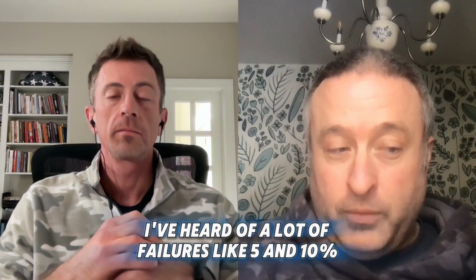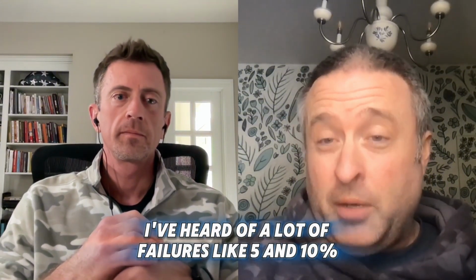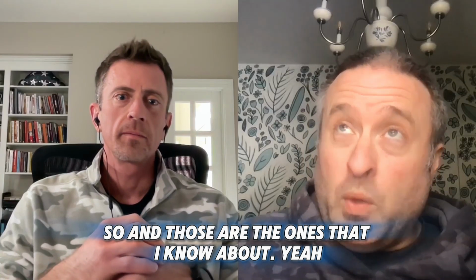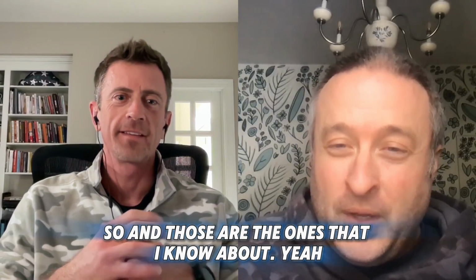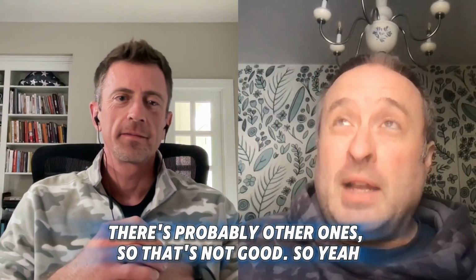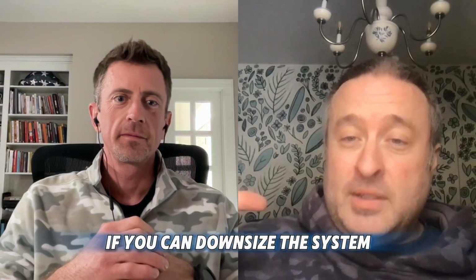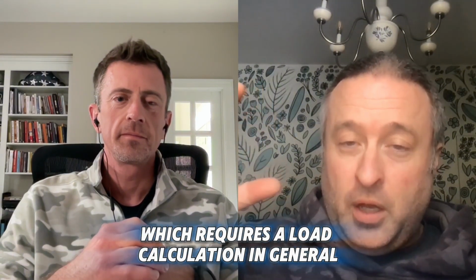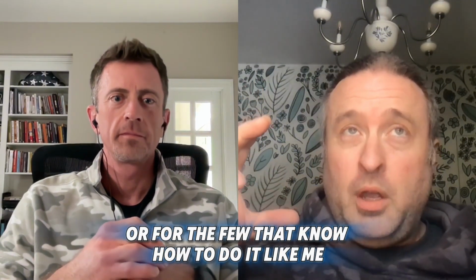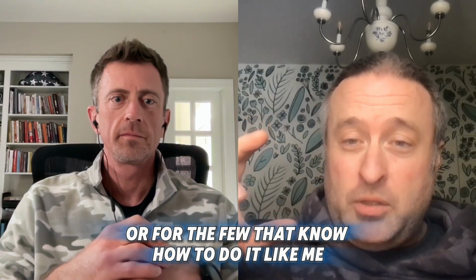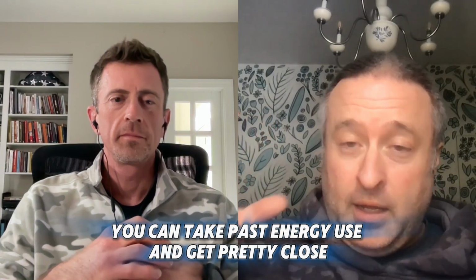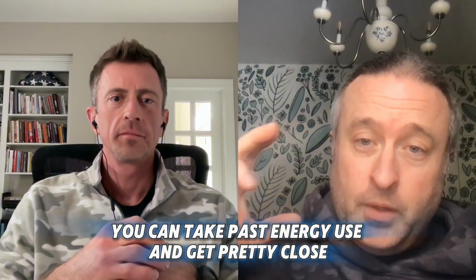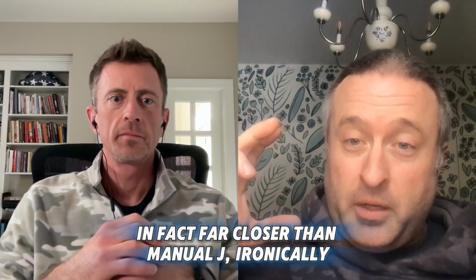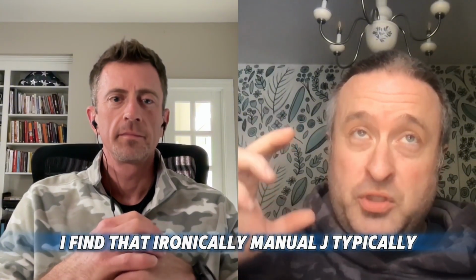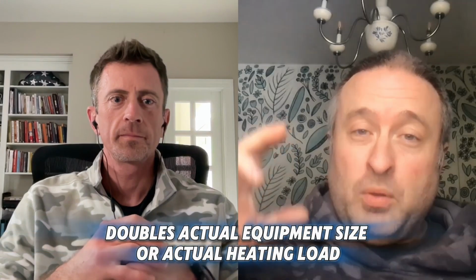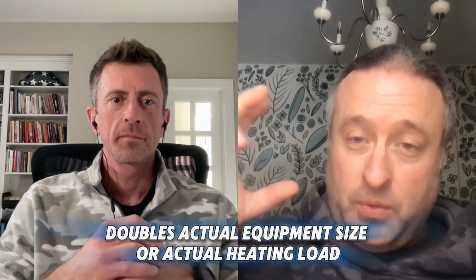Wow. I've heard of a lot of failures, like 5 and 10%. And those are the ones that I know about. Yeah. There's probably other ones. So that's not good. So, if you can downsize the system, which requires a load calculation in general, or for the few that know how to do it, like me, you can take past energy use and get pretty close. In fact, far closer than Manual J, ironically. I find that Manual J typically doubles actual equipment size or actual heating load.